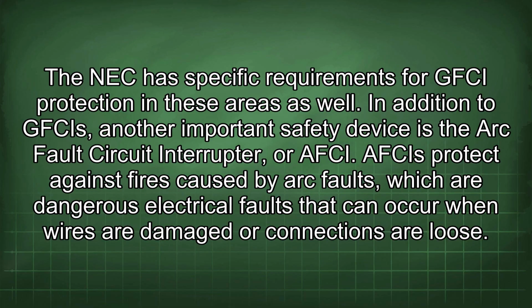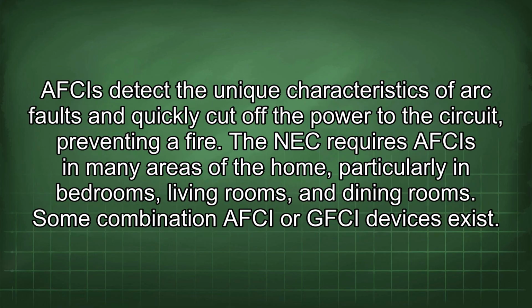In addition to GFCIs, another important safety device is the arc fault circuit interrupter, or AFCI. AFCIs protect against fires caused by arc faults, which are dangerous electrical faults that can occur when wires are damaged or connections are loose. AFCIs detect the unique characteristics of arc faults and quickly cut off the power to the circuit, preventing a fire. The NEC requires AFCIs in many areas of the home, particularly in bedrooms, living rooms, and dining rooms. Some combination AFCI and GFCI devices exist.